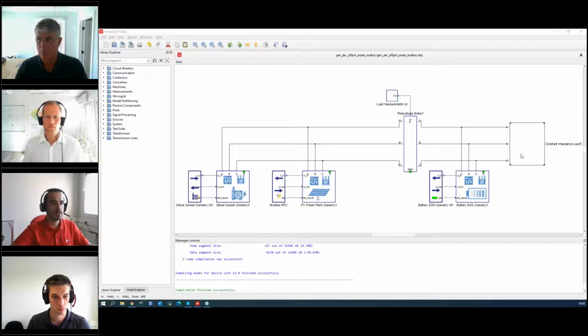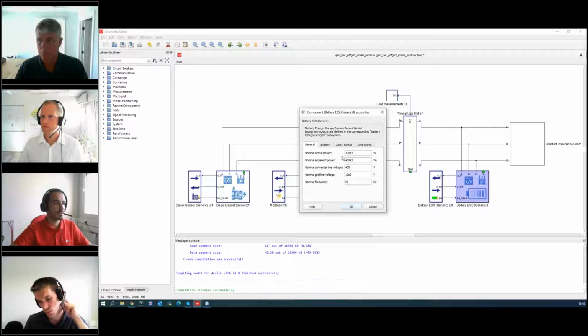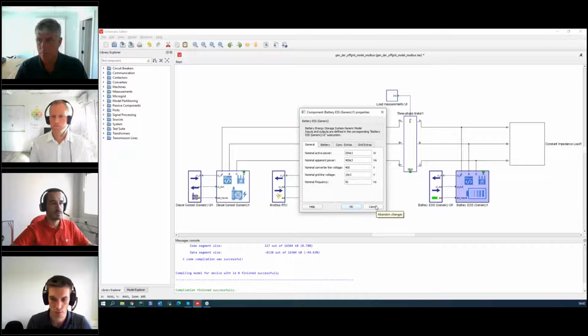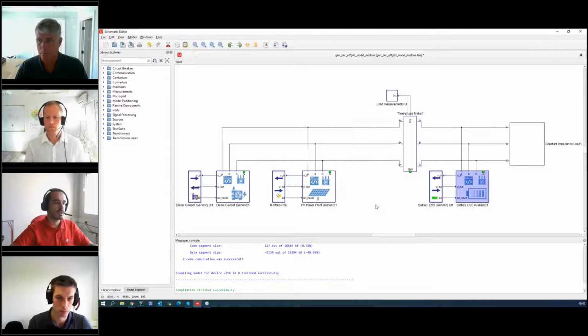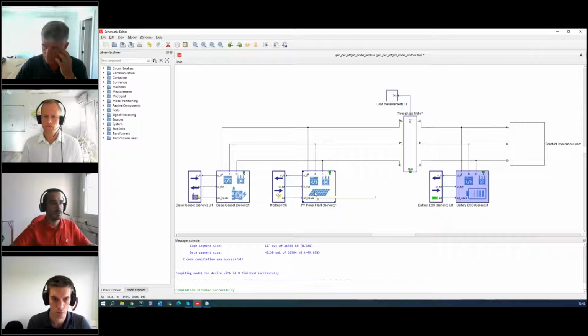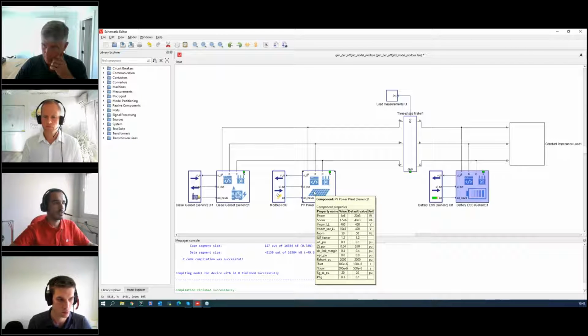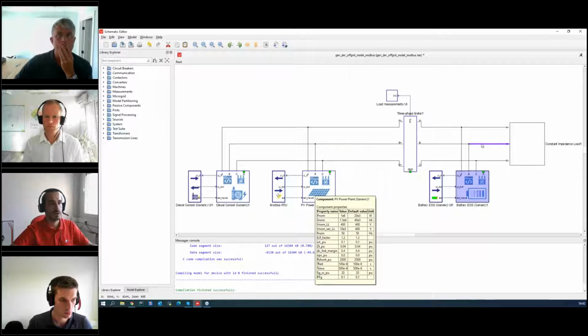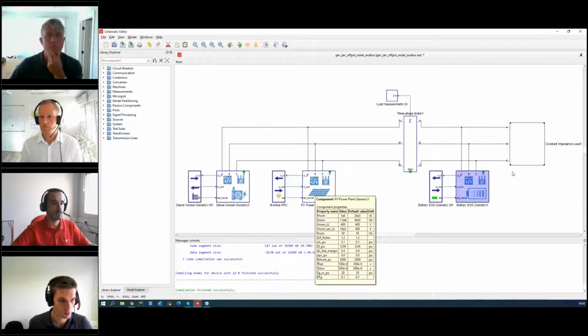Power ratings: the load is 0.5 megawatts, and the battery is 200 kilowatts, so it's not sufficient on its own to support the whole load. So in any case, either the diesel genset or the PV power should be on and providing power to the load.